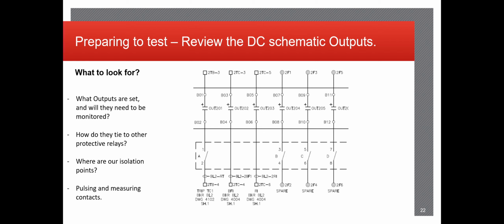Pulsing and measuring contacts is how you trigger them usually. This can be done in the command prompt or on the HMI terminal as well. Pretty much you set it for 1 second, the contact closes in for a second, opens back up, and you make sure that everything that needed to happen did. As well, you don't want to pulse a contact for too long. Usually 10 seconds is the max we'll ever do in the field, because if you hold that contact closed for too long, it might burn up, because it's usually only rated for a quick pulse and that's it.